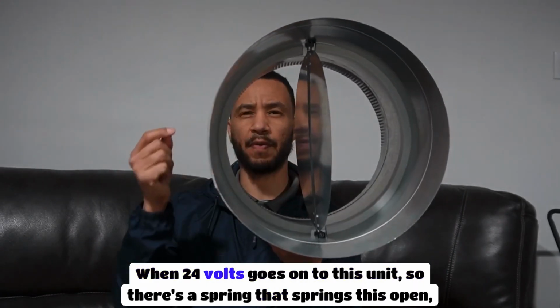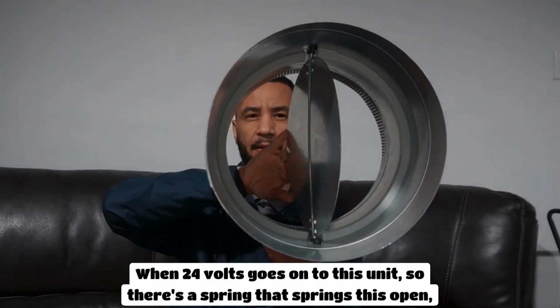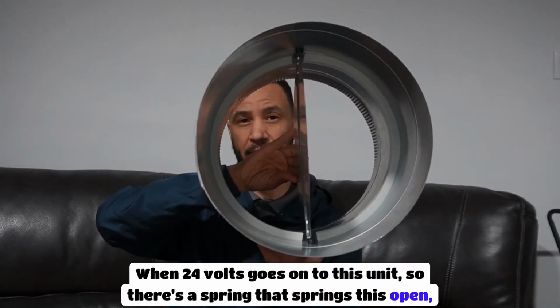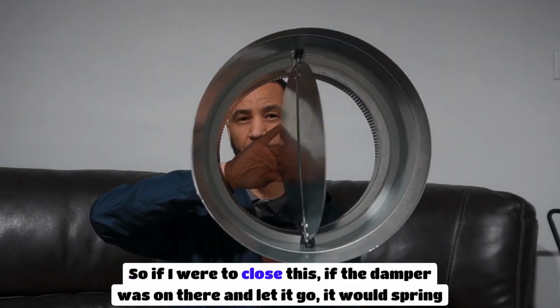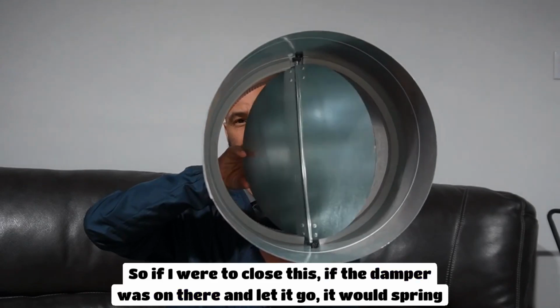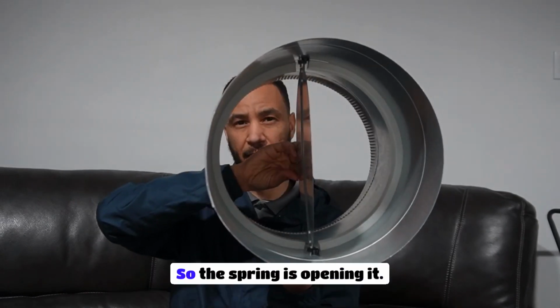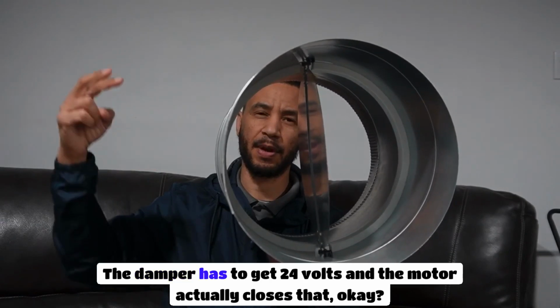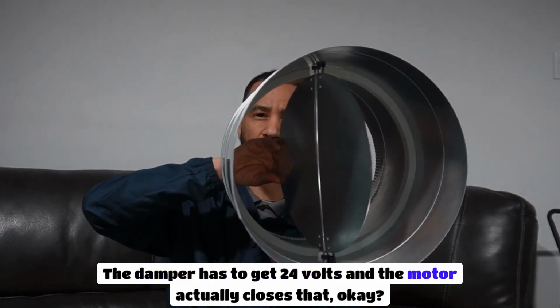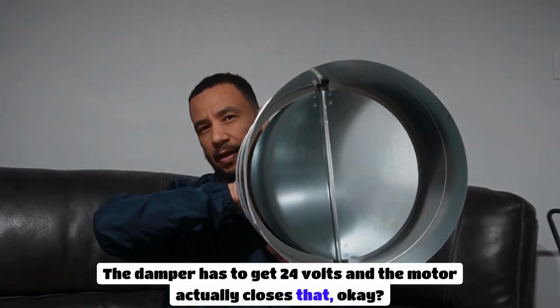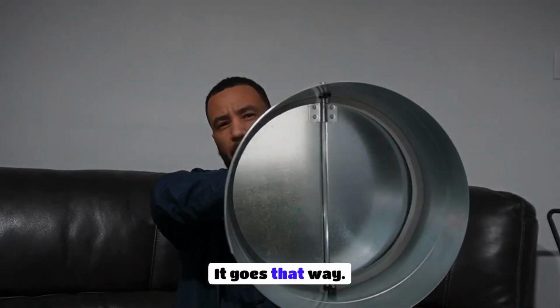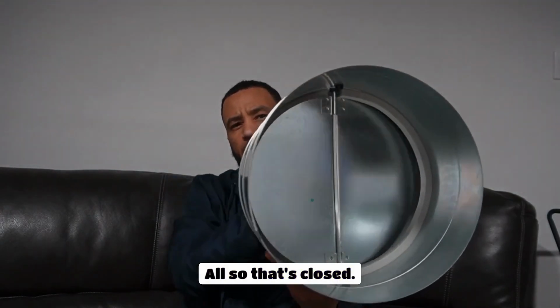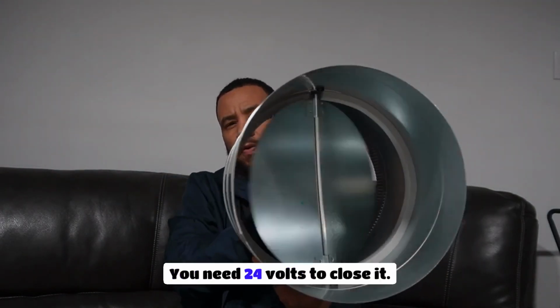When 24 volts goes on to this unit, so there's a spring that springs this open, right? So if I were to close this, if the damper was on there and let it go, it would spring just like that. So the spring is opening it. The damper has to get 24 volts and the motor actually closes that, okay? Goes that way, right? So that's closed, that's open. You need 24 volts to close it.